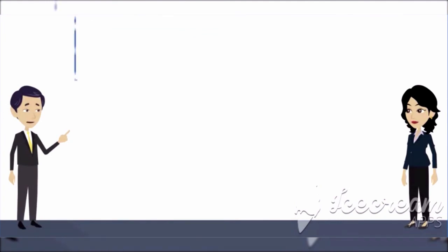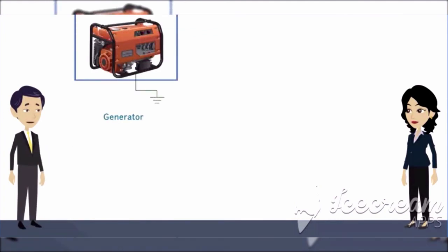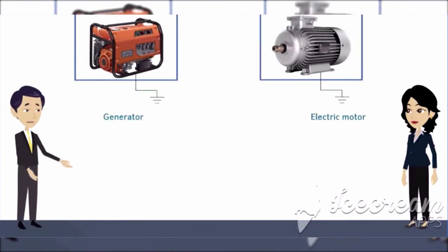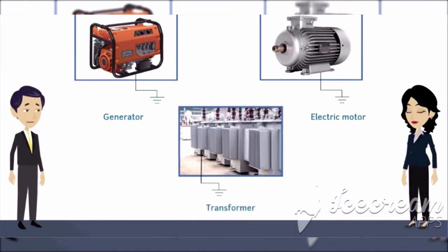Apart from these, the frame of every generator, stationary motor and as far as practicable, the portable motor and the metallic parts of transformer and any other apparatus used for regulating and controlling energy and all medium and high voltage energy consuming apparatus should be connected by 2 separate and distinct connections with earth. Wow, there is so much to it. Unbelievable. Wait, we are not done yet. Is it? Please go ahead.